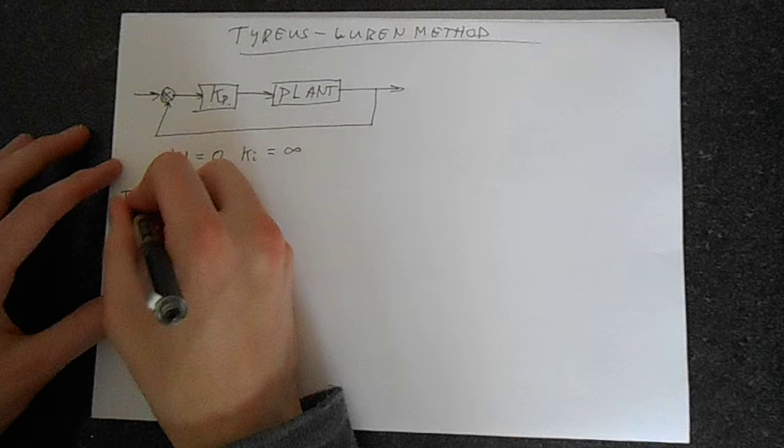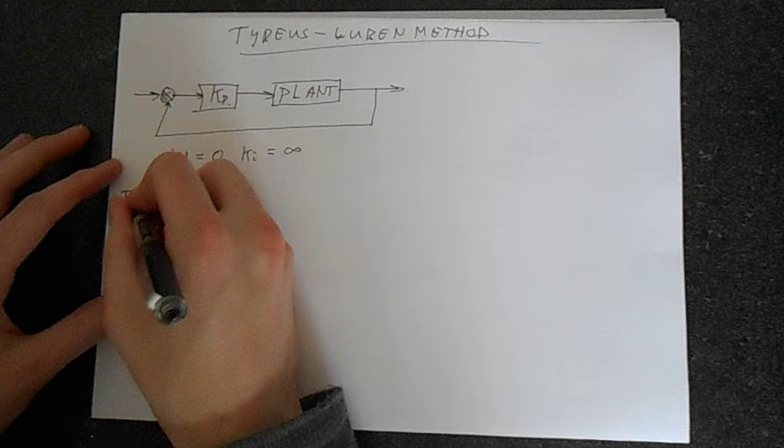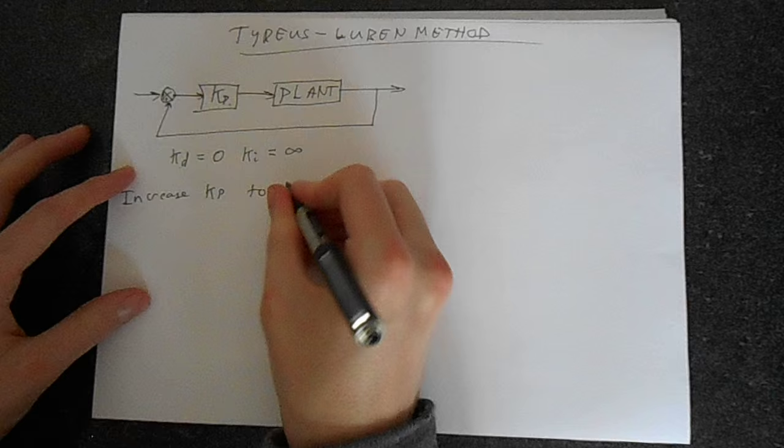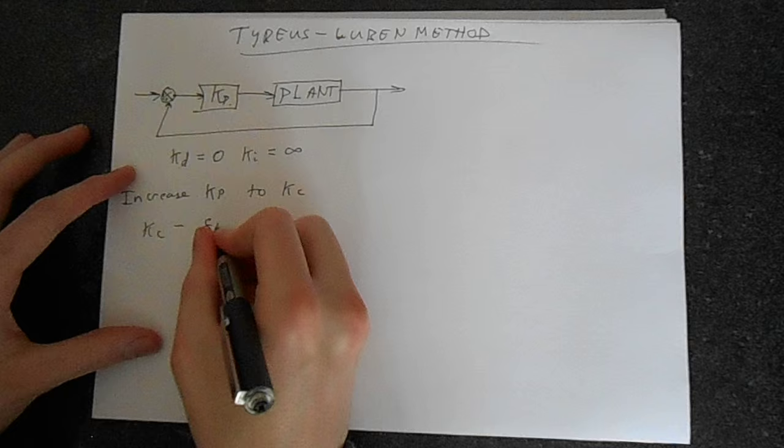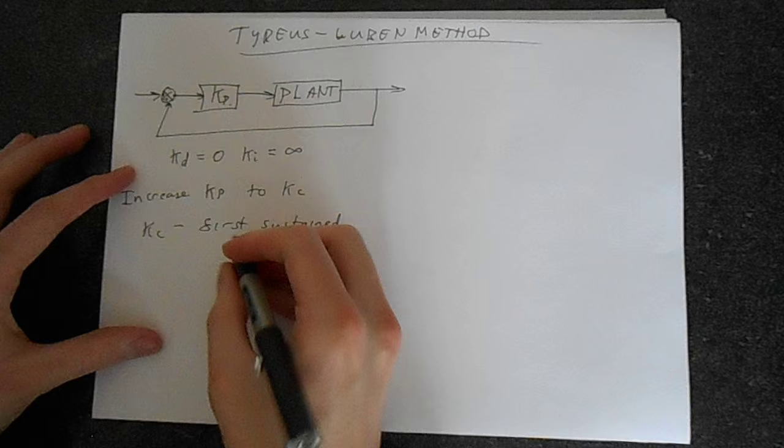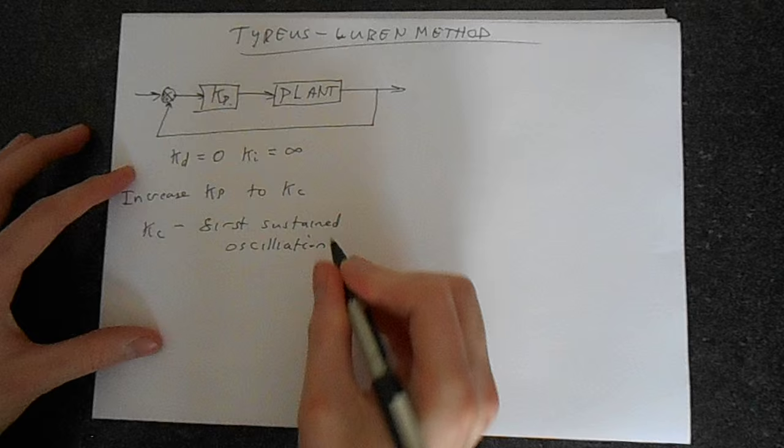Now what we do is we increase the gain KP to some value we're going to call KC, and KC is the first sustained oscillation. You keep increasing KP until you get a sustained oscillation, the very first point at which the response becomes oscillatory.